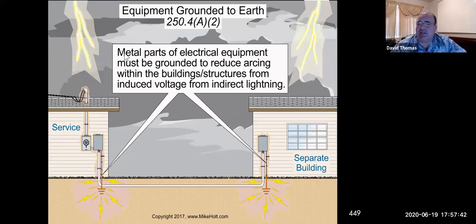Again, any electrical metal parts of electrical equipment must be grounded to reduce arcing within the building or structures from induced voltage, such as indirect lightning. So we have to make sure we ground everything properly, in case something does get into those conduits.